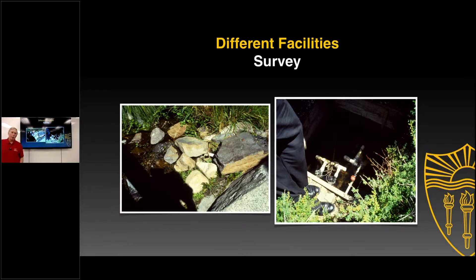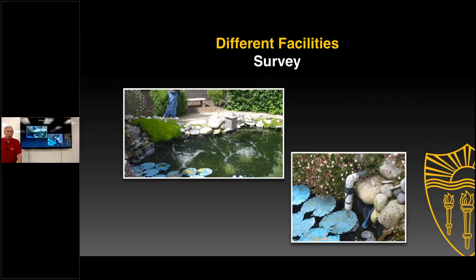What is the quality of the water in that recirculating system, in that stream? It may be a little more obvious when you walk up to the fish pond — the fish love that nice green water. But you look over in the corner in that lower right-hand area, you can see where the water line comes in and is below the rim, filling into that pool. We find quite frequently that people look past water features and don't consider the fact that there may be potable water interconnected. Even in ponds and water features, we need to look carefully at where the water is coming from.